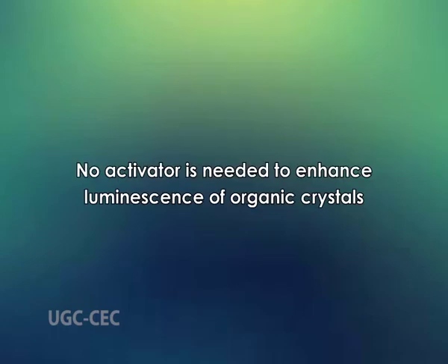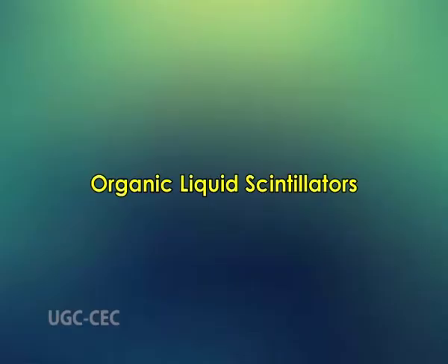No activator is needed to enhance the luminescence of organic crystals. In fact, any impurities are undesirable because their presence reduces the light output, and for this reason the material used to make the crystal is purified. Next is organic liquid scintillators.